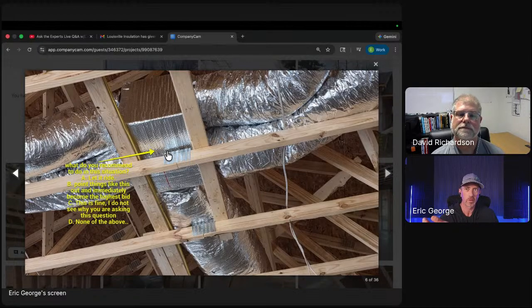In our climate zone, you have to have R8 duct insulation to pass code. What I've seen a lot of HVAC guys do is just put two layers of this stuff on and call it good for R8. But again, there's no air gap between the duct and the bubble wrap, so doubling up directly on top of the sheet metal is not going to give you an effective R8.